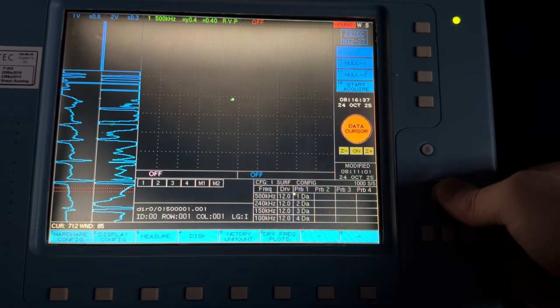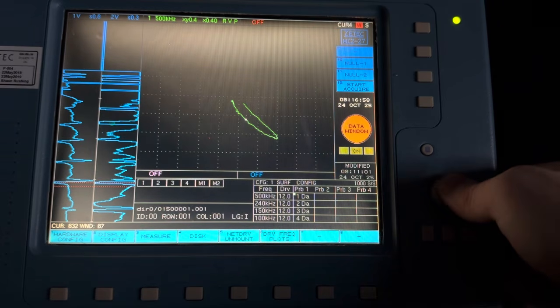So this is the 100% hole, and I've already calibrated this particular indication. The 100% through-wall hole starts down and to the right and goes up to null, and then the second coil will go in the opposite polarity and come back to null as the pair of coils goes past that 100% flaw. Now, to get that whole flaw in the window, I have to make my window a little bit bigger here.